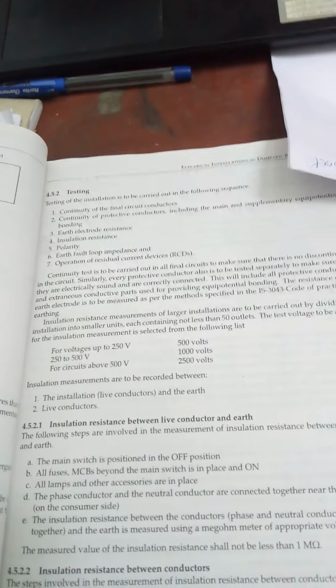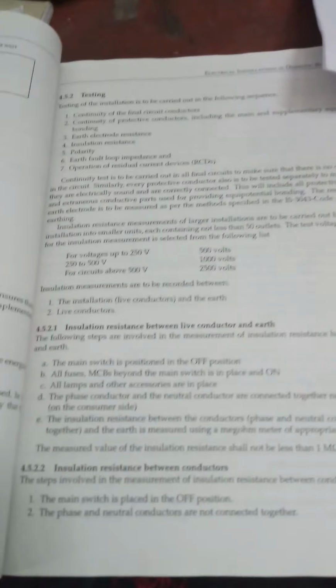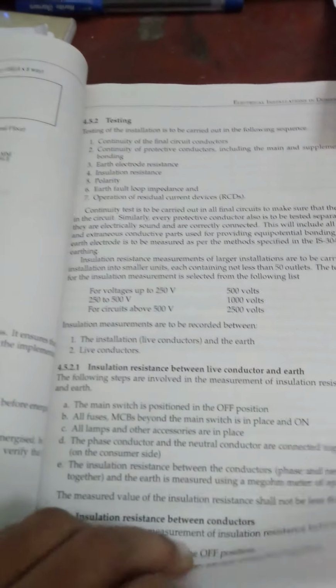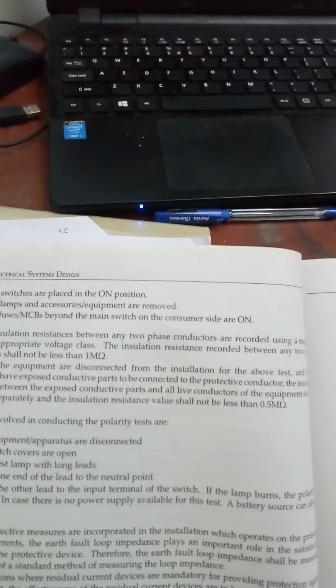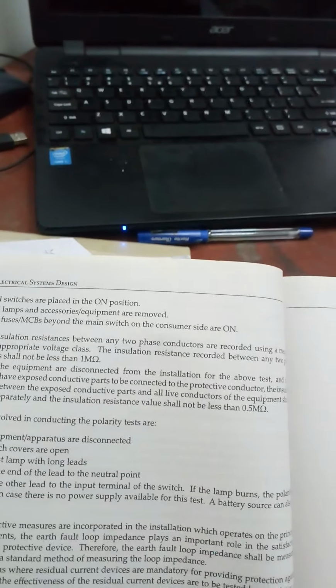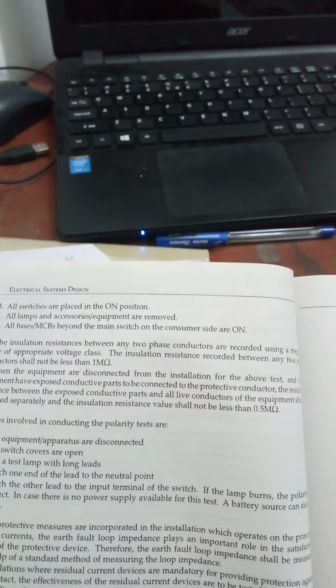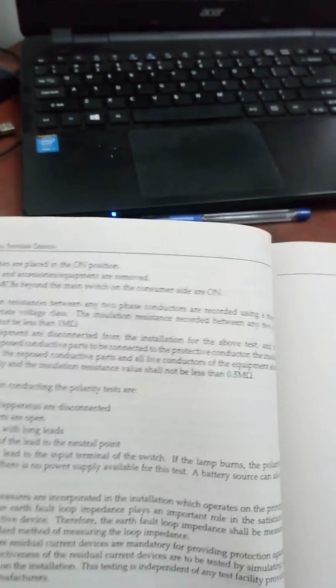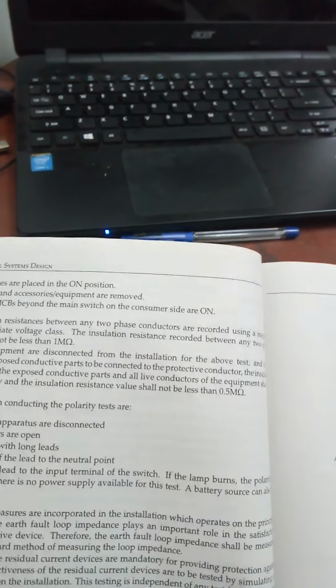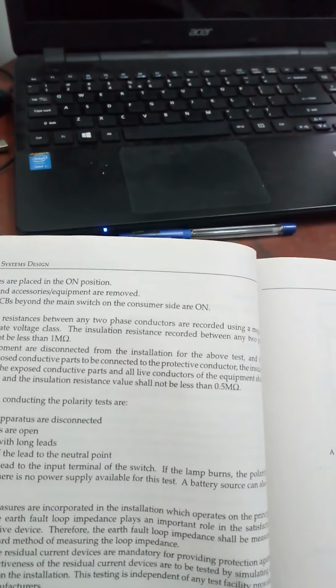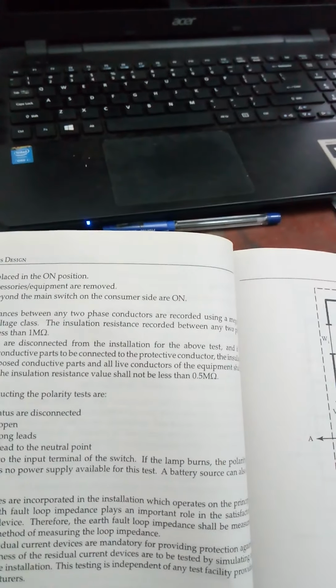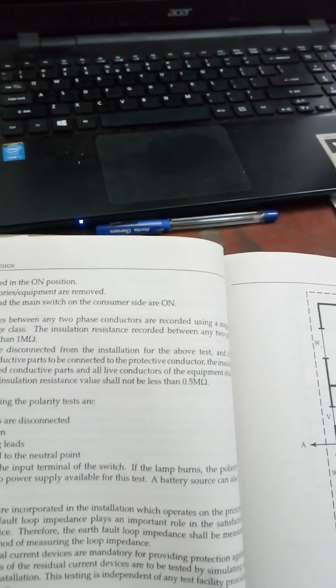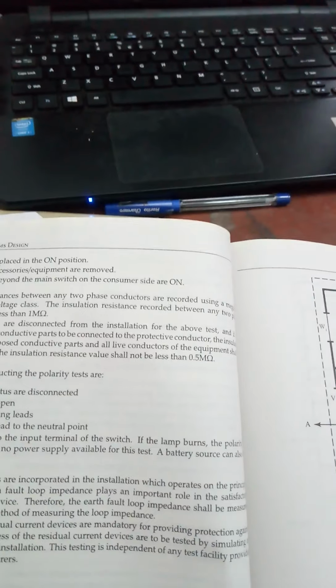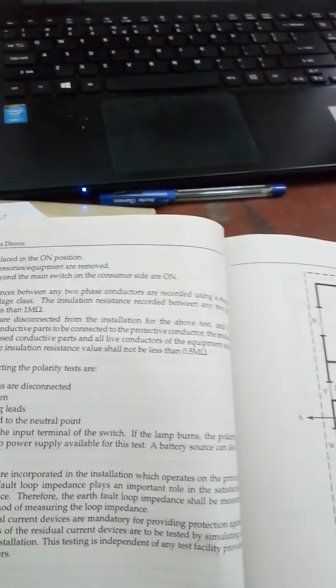For measuring insulation between conductors, the following steps are followed. The main switch is placed in the off position. The phase and the neutral conductors are not connected together. All switches are in the on position. All lamps are removed. All fuses beyond the main switch of the consumers are kept on. The insulation resistance between the two phases is recorded using a megohm meter, and the insulation recorded should not be less than 1 megohm. When equipment is disconnected from the installation for the above test, and if the equipment has exposed conductive parts to be connected to the protective conductor, the insulation resistance between the exposed conductive parts and live conductors shall be measured separately.